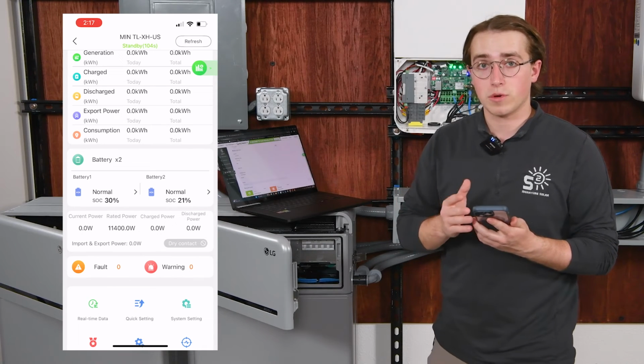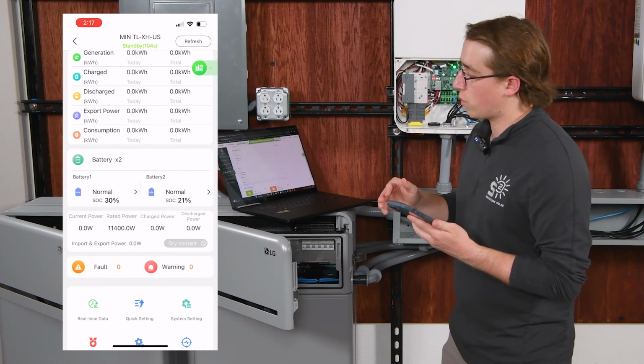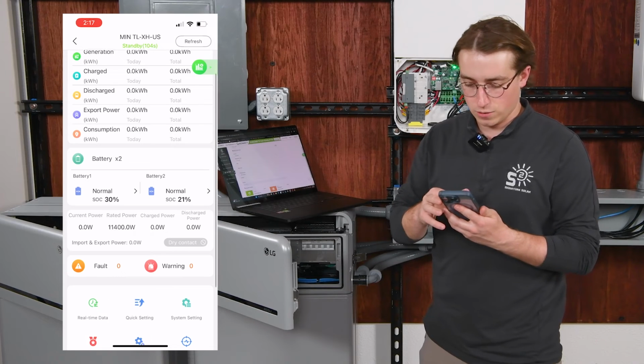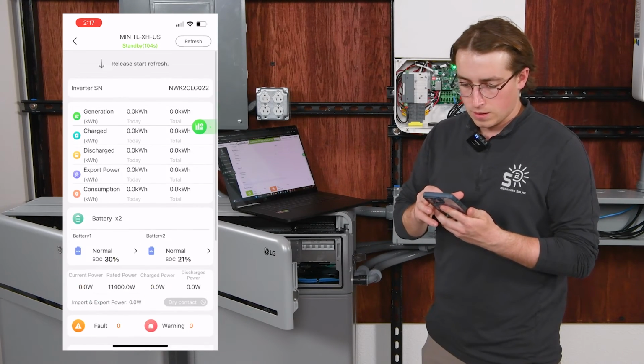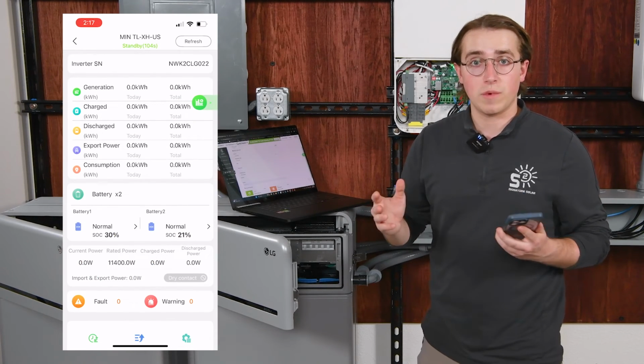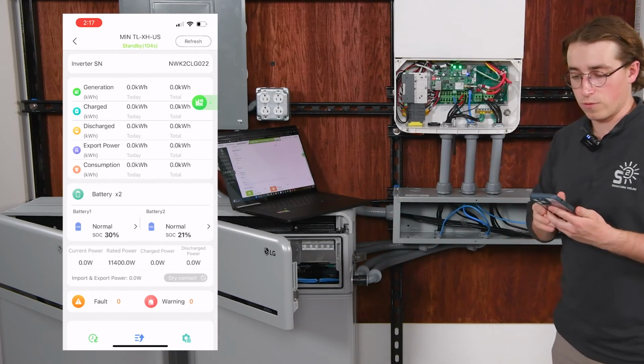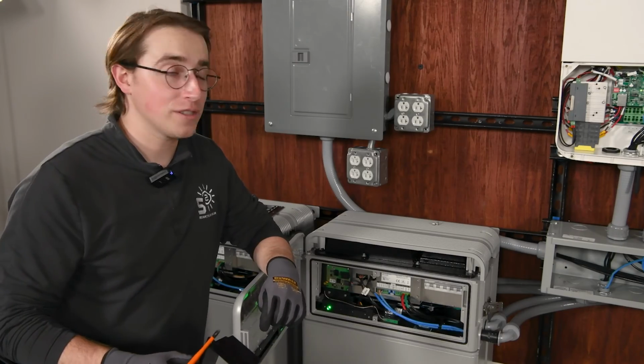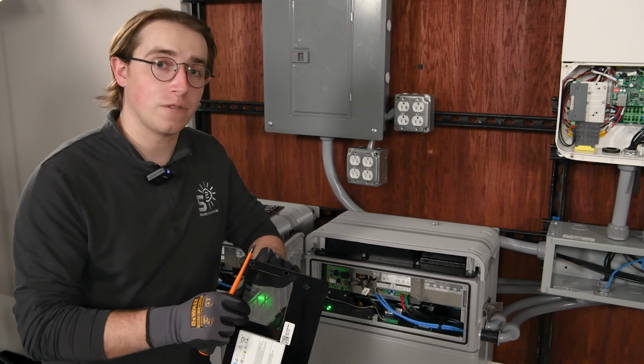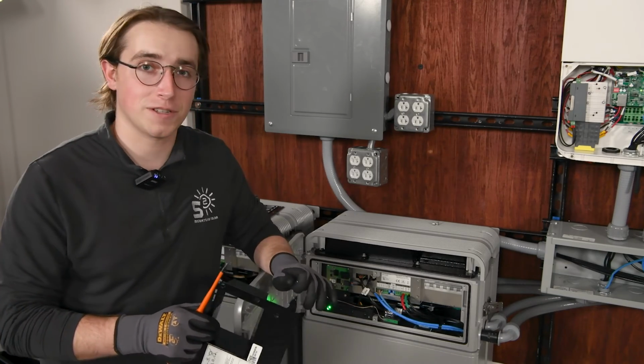Battery 1 is at 30% state of charge, and battery 2 is at 21% state of charge, so I'll need to get those charged up. But outside of that, that is the overall quick commissioning guide for the Growatt 11.4 inverter. With the system commissioned and everything up and running, we're going to go ahead and put the face covers back on and lock up the rest of the system.